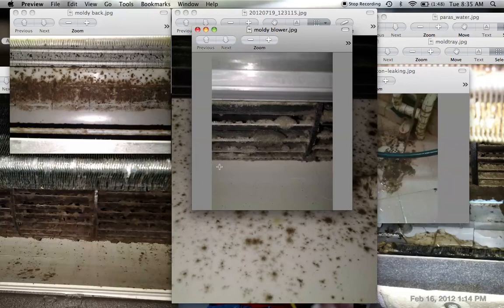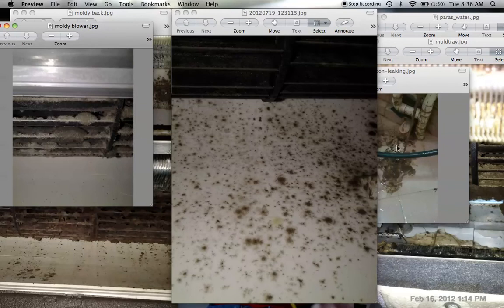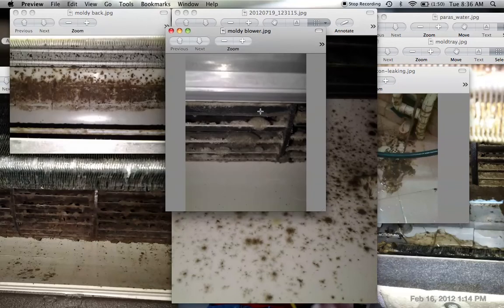So what exactly is happening is that when the air has these oil particles and you turn on the aircon, it scoops the air into the system. It deposits a thin layer of oil on the back part of the aircon, a thin layer on the blower, and a thin layer of oil on the fan coil itself. And the aircon, being cold, has condensation.